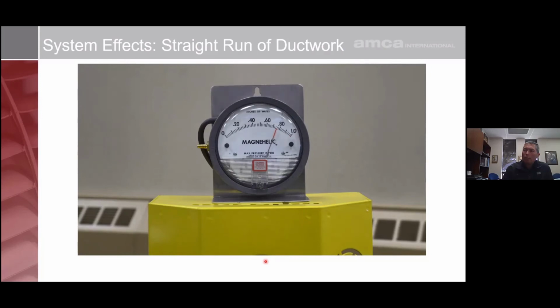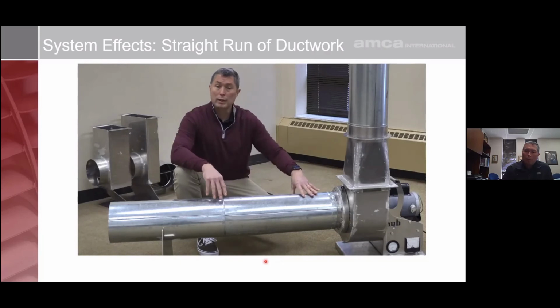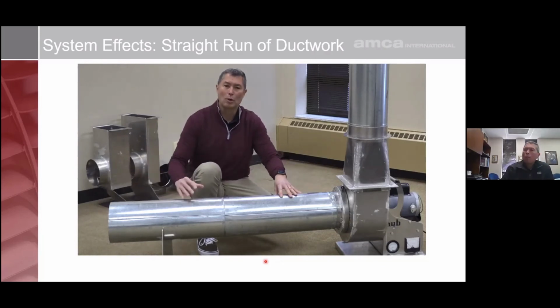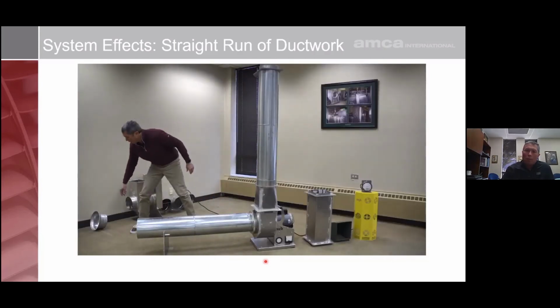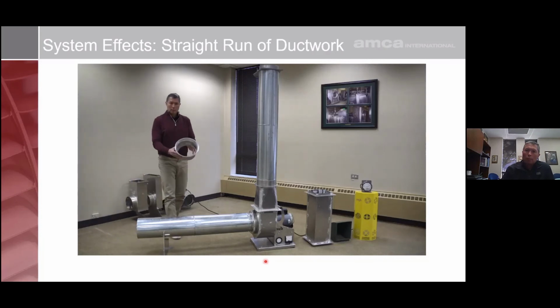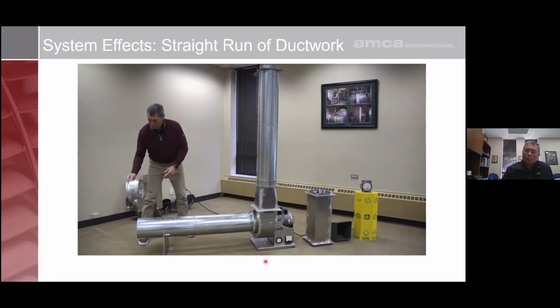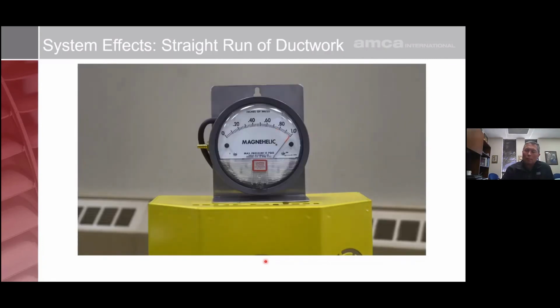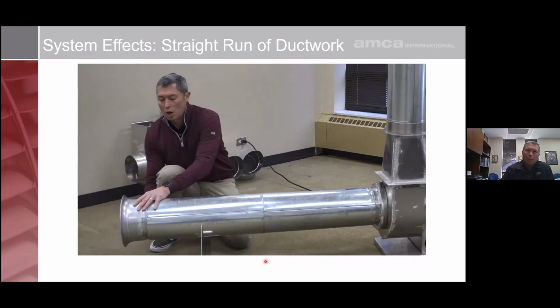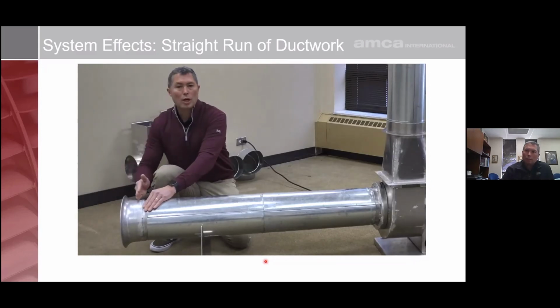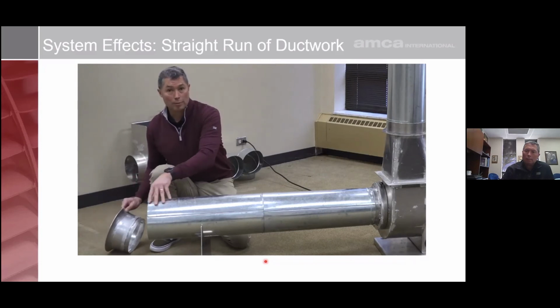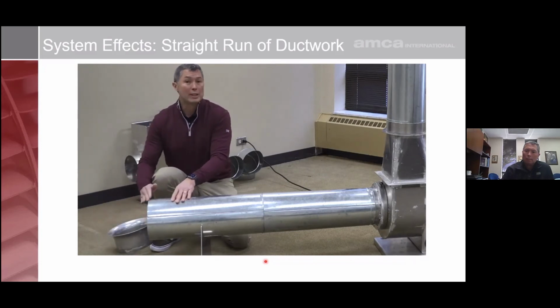Now, a lot of people think that that's associated with friction loss through this ductwork, the amount of effort that it takes to pull air over a piece of sheet metal or a piece of Schedule 40 pipe. Now, if we add this venturi to the inlet, just a plain venturi, see what happens. You'll notice that almost all the losses associated with the straight run of ductwork are gone, that there's virtually no losses. And what you soon realize is that those losses are associated with the entry loss over this sharp-edged orifice. And that entry loss is pretty significant, almost 1/10 of an inch.